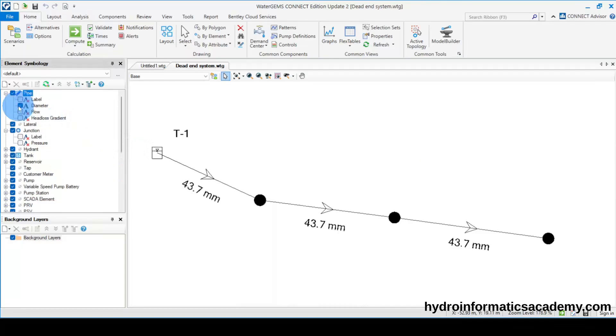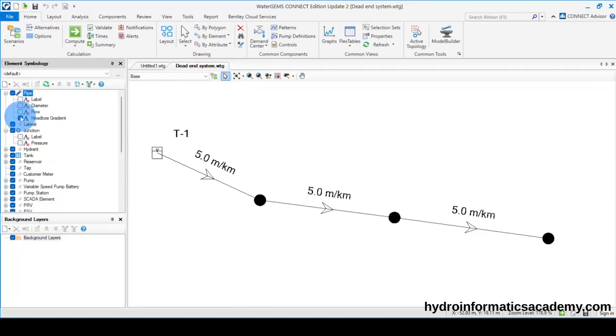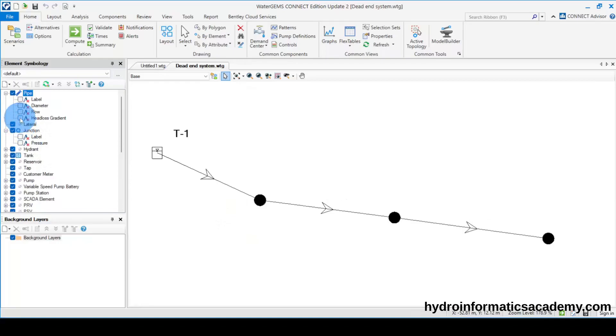Remember, the value of the diameter we are using here is the internal diameter of the pipe. If you want to learn how to get the internal diameter of any pipe, a link to that tutorial will be in the description below. If I activate the head loss gradient or unit head loss, you can tell this value is within the acceptable head loss range values, depending on which design manual you're using.